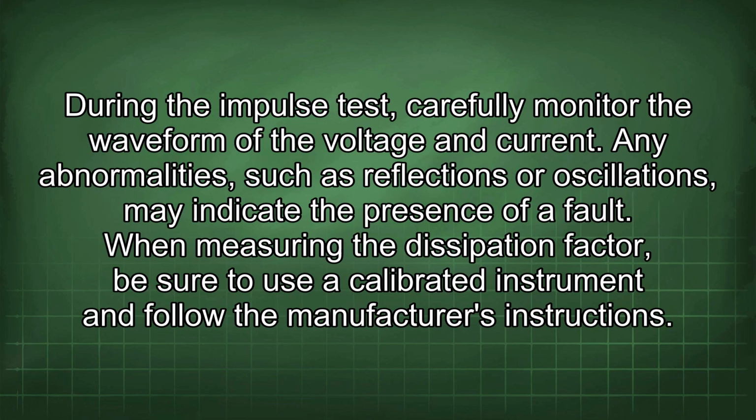During the impulse test, carefully monitor the waveform of the voltage and current. Any abnormalities, such as reflections or oscillations, may indicate the presence of a fault. When measuring the dissipation factor, be sure to use a calibrated instrument and follow the manufacturer's instructions.